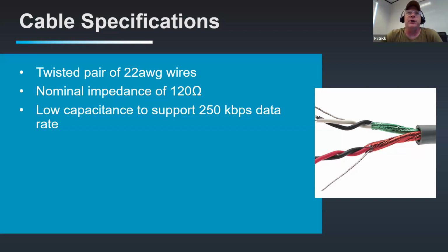Those of you that are using RDM in things: the receivers nowadays, like a lighting fixture or anything that's receiving DMX from the sending device, are pretty robust in that they don't necessarily need to be terminated anymore. But RDM is a two-way communication, so RDM will get very cranky if it's unterminated, and you can lose that capability to get bidirectional communication with your receiving devices.